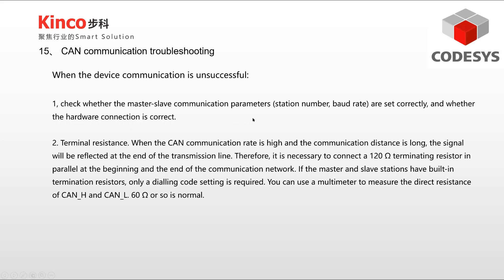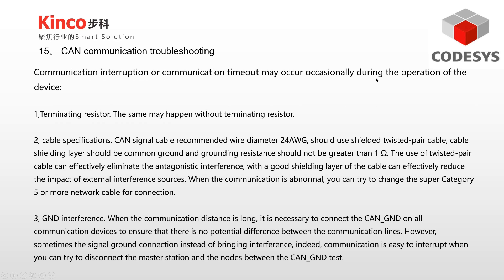Second, check the terminal resistance. When the CAN communication rate is high and the communication distance is long, the signal will be reflected at the end of the transmission line. Therefore, it is necessary to connect a 120-ohm terminating resistor in parallel at both the beginning and end of the communication network. If the master and slave stations have built-in termination resistors, only a DIP switch setting is required. You can use a multimeter to measure the direct resistance of CAN-H and CAN-L — around 60 ohms is normal. Communication interruption or timeout may occasionally occur during operation, so first check the terminating resistor, as this may happen without one.